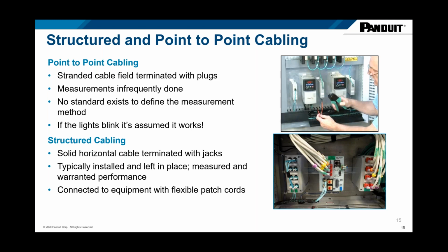Structured cabling to what is referred to as the horizontal connections or the downlinks is also recommended by 1005A. We're down at that EO level in the model. Extending structured cabling to this level provides greater testing capability when commissioning and troubleshooting the network at the edge of the network, or in cabling subsystem 1 in the TIA terms. In certain cases, such as on-machine field connections, point-to-point cabling is the only option. And the test methods for point-to-point are different than with structured cabling using jacks. So different tests indicate the performance based on point-to-point or structured cabling.